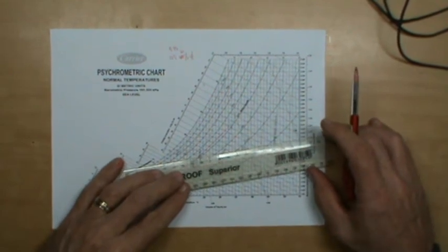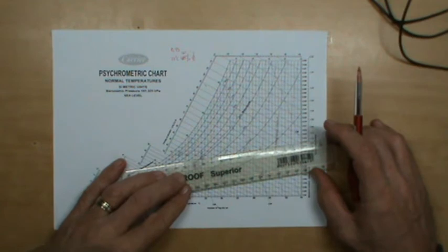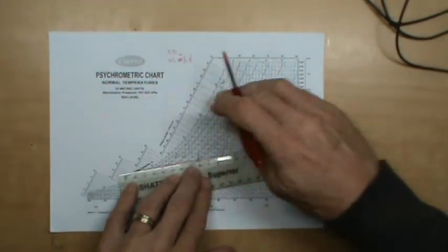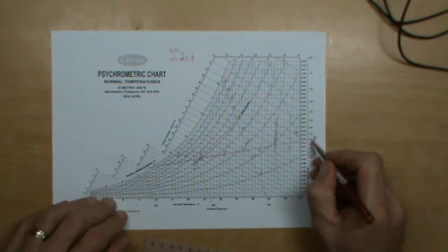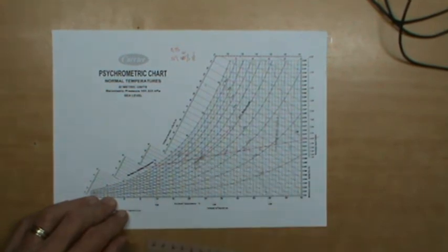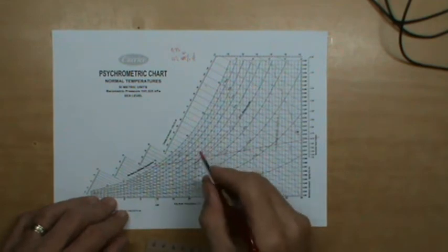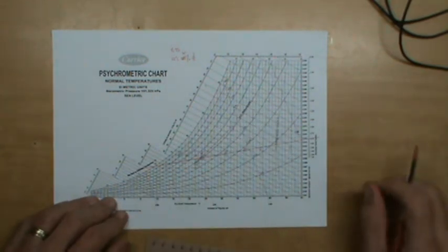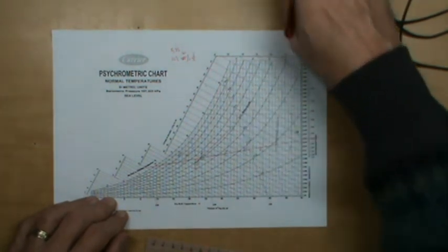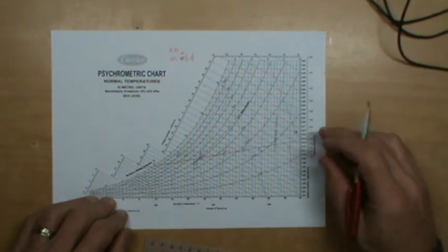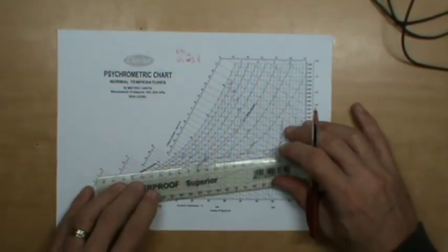From the swivel point, do 0.75 over there. We draw a line. I'm going to just draw it in red over there so you can see it nice and clearly. That is between 0.75 over there and the swivel point of 24 degrees Celsius and 50% relative humidity. But now remember, in the previous one, we drew a line from state point 2 to the saturation line over there. But now we've got to do exactly the same thing over here, but only starting at 22 degrees Celsius and 50% relative humidity. The way we do it is we draw another line that is parallel to that line that you've just drawn.